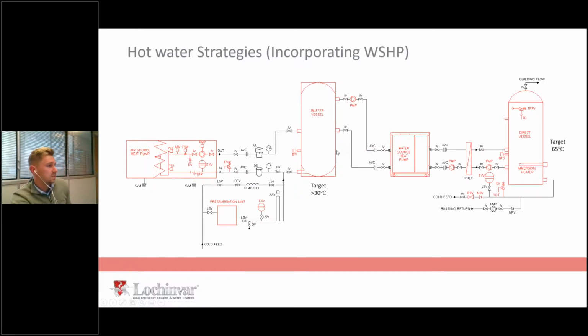Solution number two, same sort of setup, but we've got a water source heat pump producing hot water. And this would be when you want a hot water system that's going to be working at a particularly high temperature. So let's say you've got a bovine processing facility, so all of the pressure jets need to flow at 70 degrees centigrade because it's sanitary. Well, fair enough, you would do that by using this boost format, and you would still have those incredibly high efficiencies while producing that much hot water ready for your washdown.